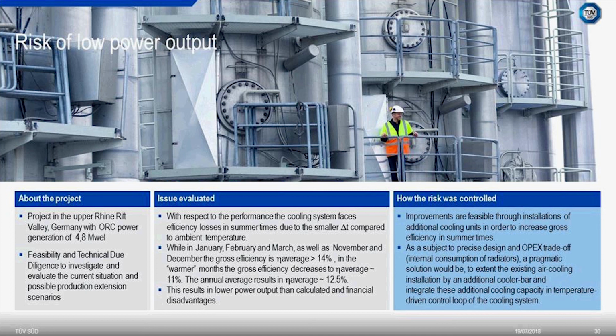Our solution for that: we advised the operator and investor to improve the whole feasibility through installation of additional cooling units on the roof. They had enough space for it, in order to increase the gross efficiency in summer times. So we had to cope with this delta T with an additional installation. As a subject to the precise design and the OPEX trade-off, of course, a pragmatic solution could be to extend the existing air cooling installation by an additional cooler bay and integrate this additional cooling capacity in the temperature-driven control loop of the cooling system, which means that we have a higher cooling power which compensates the degraded delta T for the summertime season.